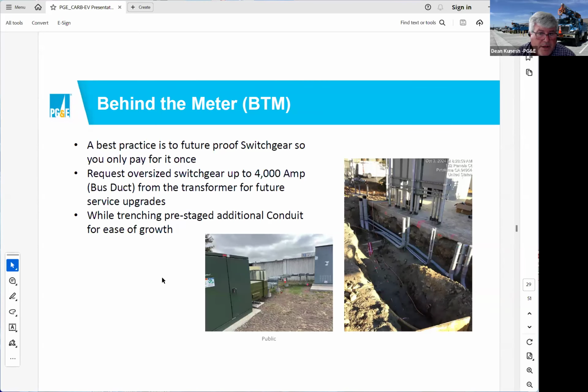Here's some behind the meter examples. A best practice is to future-proof your switchgear. This is 4,000 amp switchgear, which requires on a 480 volt circuit a bus duct. This area right here, going between the green transformer and the gray switchgear, is bus duct - 4,000 amp bus duct. This is future-proofing this site with the largest type of amperage you can go on a secondary service with PG&E.